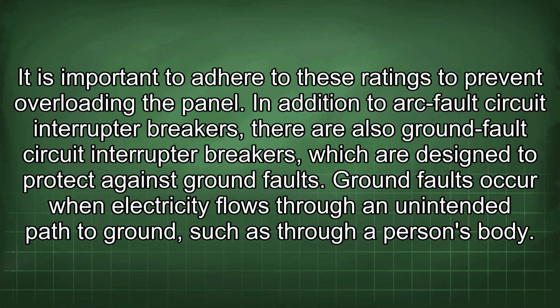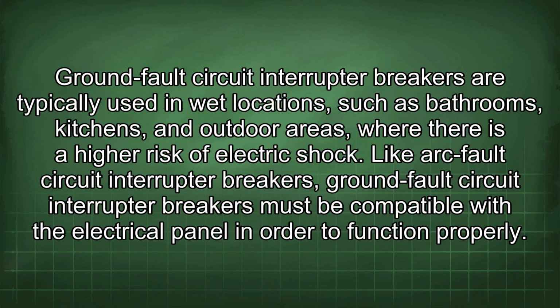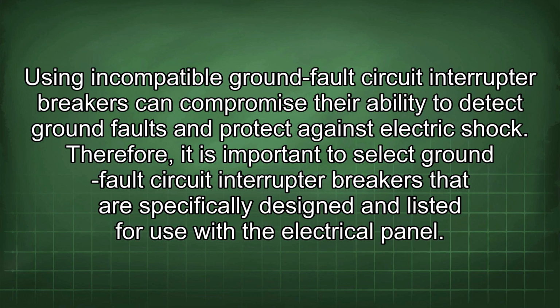In addition to arc fault circuit interrupter breakers, there are also ground fault circuit interrupter breakers, which are designed to protect against ground faults. Ground faults occur when electricity flows through an unintended path to ground, such as through a person's body. Ground fault circuit interrupter breakers are typically used in wet locations, such as bathrooms, kitchens, and outdoor areas, where there is a higher risk of electric shock. Like arc fault circuit interrupter breakers, ground fault circuit interrupter breakers must be compatible with the electrical panel in order to function properly. Using incompatible ground fault circuit interrupter breakers can compromise their ability to detect ground faults and protect against electric shock.